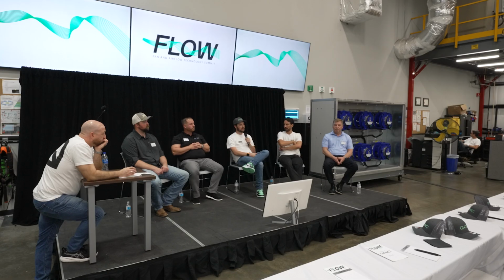We're trying to figure out where the best point to apply harmonic filtration is. We've explored solutions where you apply a harmonic filter upstream of our control panel, filtering the entire system downstream from that. We've also talked about applying a harmonic filter at every fan controller level, sizing it for up to 9 motors that controller manages, and also at the motor level itself, since you can buy EC motors with a filter already built in. So it's about putting the components in the right spot and figuring out the most efficient and resilient way to do it.